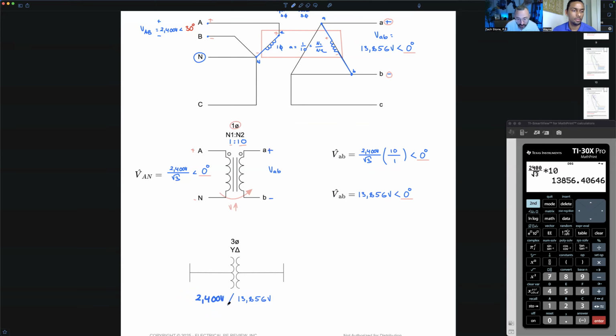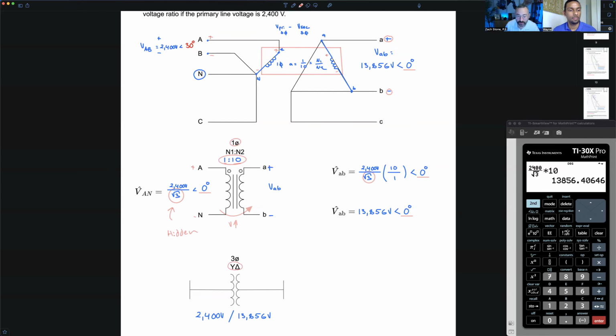We'll make that a slash so it doesn't look like we're dividing. Notice that this is a little different than the 1 to 10 ratio of the single phase transformer compared to the three-phase transformer. 2400 times 10 is not 13.8 kV. So here's what we typically call the hidden square root of 3. We had to include it because we're using our single phase turns ratio, and our transformer is connected Y delta.